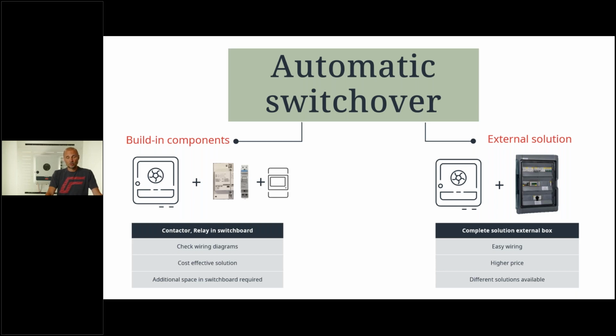The other one is the external solution. Here we have, for example, an NV Tech box, from a supplier from Europe, from Germany, who is making these boxes for us, and he's preparing all the required components, like the contactor, the fusing for the inverter, the smart meter is also included, and the relay. This has a higher price, but it's of course the easier wiring. You don't need to do a lot of wiring. You just take your 3-phase out of your switchboard and into the inverter, and back to the switchboard again, and you need 1 communication cable to the inverter. There are different solutions available, so please check your country. You can also find on their webpage a configurator tool where you can decide which box you need in your country.